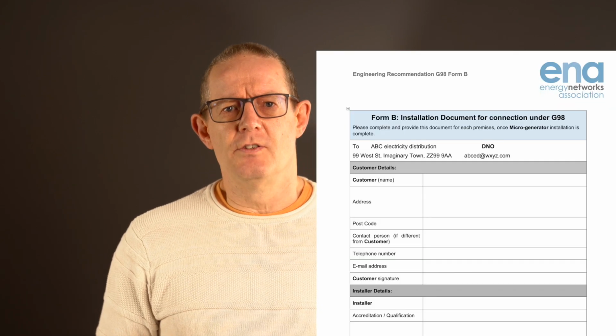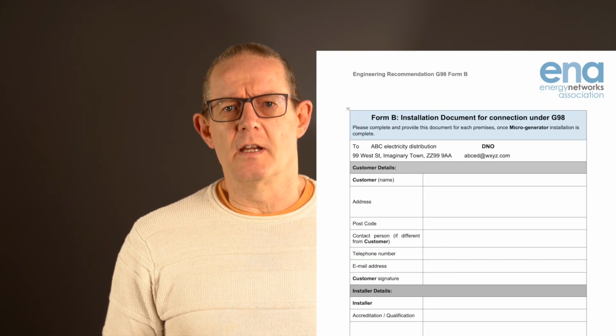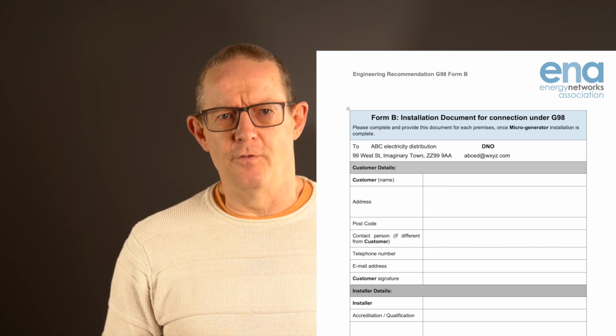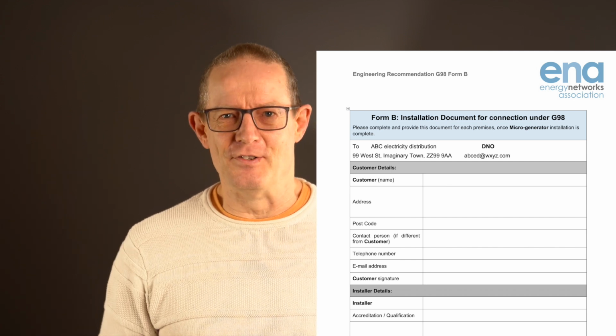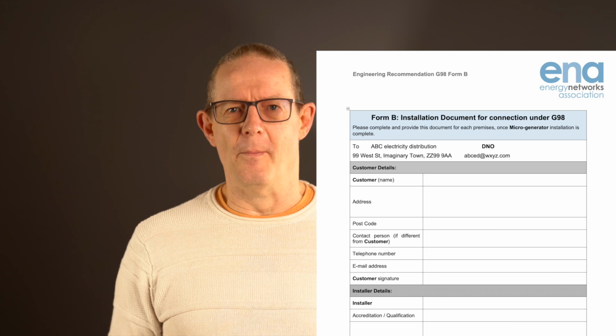If your installation has an aggregate rating of 16 amps, or 3.68 kilowatts per phase, or less, your solar installer just needs to send the DNO a completed G98 Form B microgeneration single premises commissioning form. In short, it's a pre-approved installation, though there are a few caveats around that.